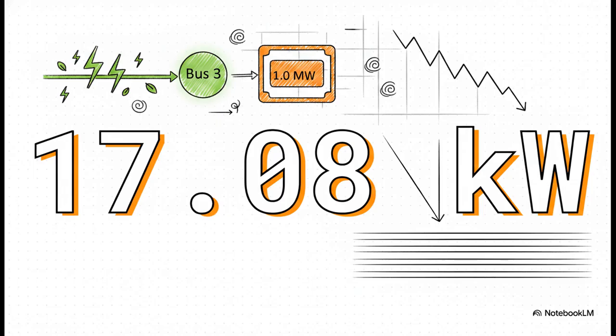By simulating generations of evolution, the genetic algorithm found the exact optimal sweet spot, bus 3, and it determined the exact optimal size, a 1.0 megawatt generator. By dropping this specific generator into this highly specific mathematical sweet spot, line losses dropped dramatically, and the voltage profile across the entire network smoothed out perfectly.